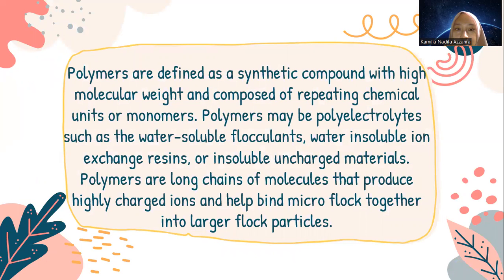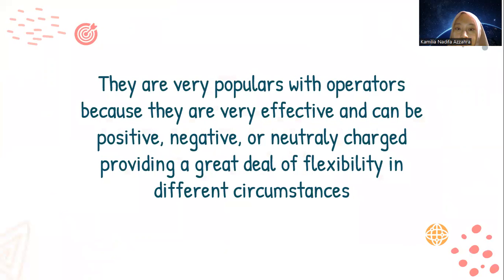Polymers are defined as synthetic compounds with high molecular weight and composed of repeating chemical units or monomers. Polymers may be polyelectrolytes such as the water-soluble flocculants, water-insoluble ion exchange resins, or insoluble uncharged materials. Polymers are long chains of molecules that produce highly charged ions and hold microfloc together into larger particles. They are very popular with operators because they are very effective and can be positive, negative, or neutrally charged, providing a great deal of flexibility in different circumstances.